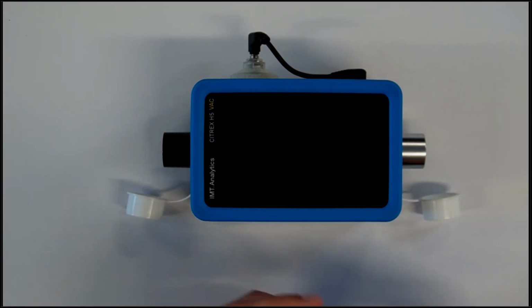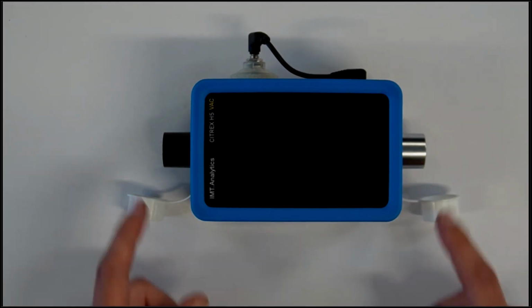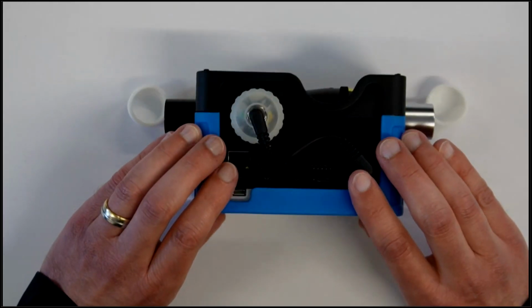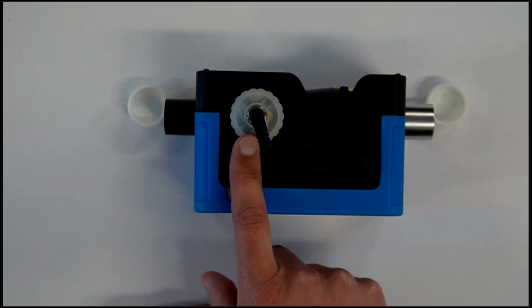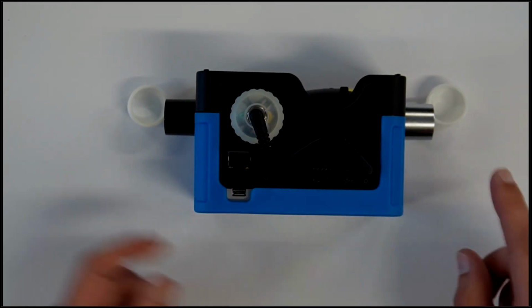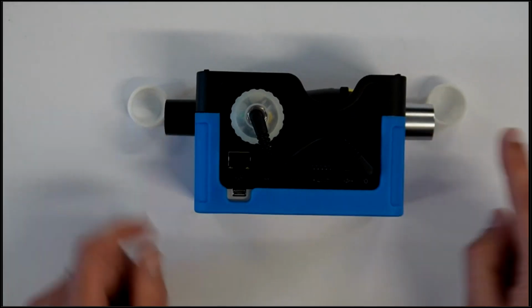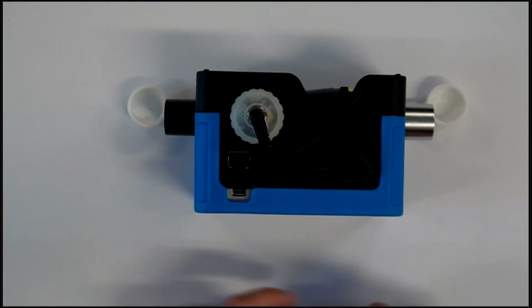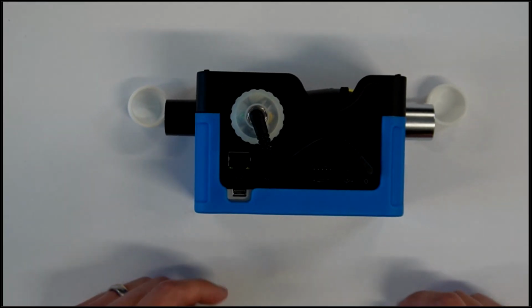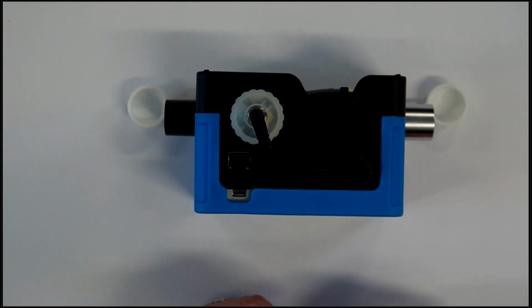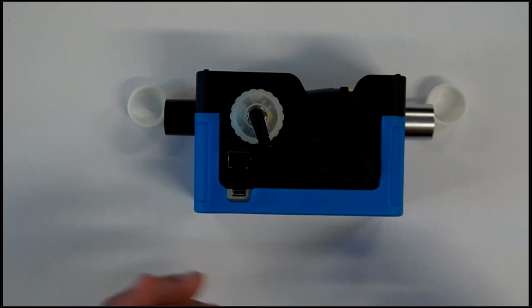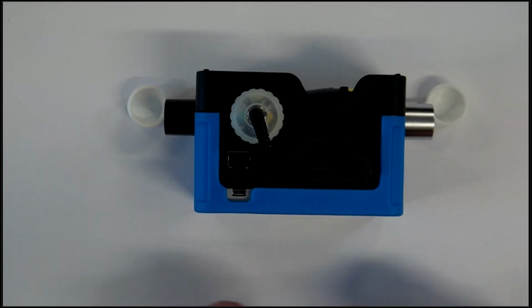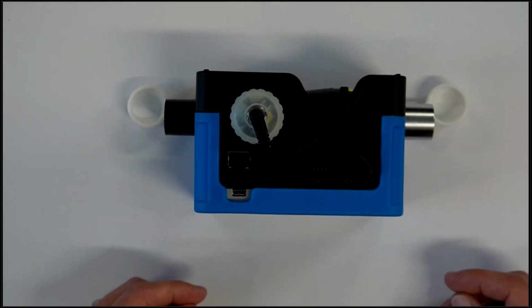We call the CITREX H5 an all-in-one device because all other relevant parameters are also measured right inside the flow channel. If you take a look at the side of the device, we have a replaceable oxygen sensor, and that one is measuring the oxygen concentration of the gas flowing through the flow channel right here inside the device. The same applies for the temperature of the gas and the pressure. It's all being measured right inside the flow channel, so there's no need for external components, no need to tee in anything. It's all right there where you would expect it.